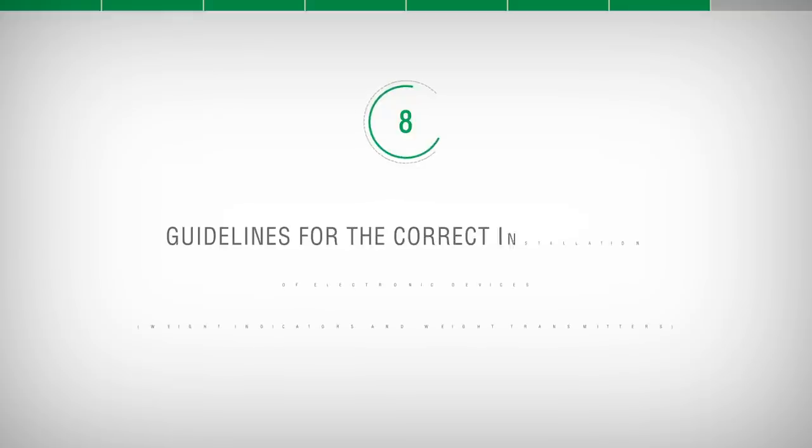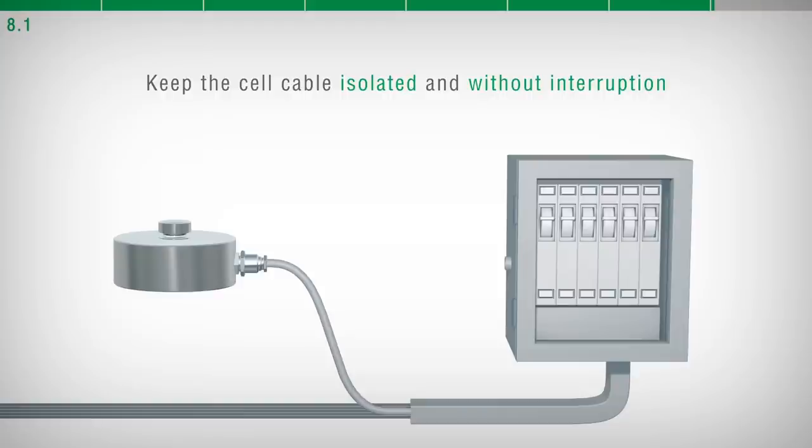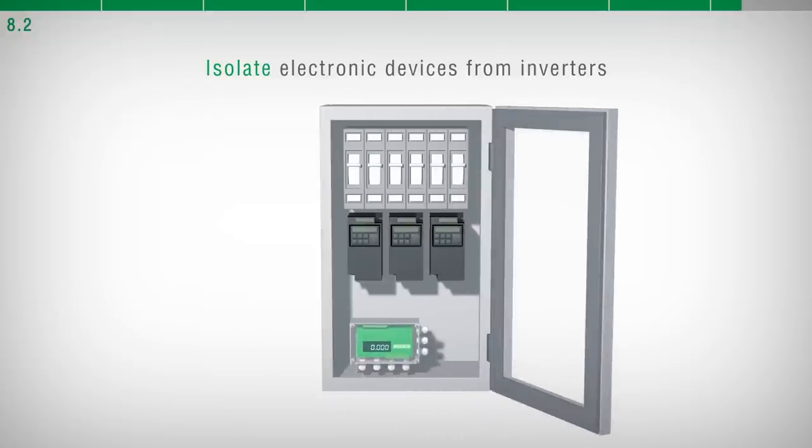Guidelines for the correct installation of electronic devices, weight indicators, and weight transmitters. The load cell cable must be autonomous and not pass through the wire way with other cables. It is recommended to connect it directly to the weight indicator or transmitter without interruptions and without terminal boards. It is recommended not to install electronic devices in an electrical panel containing inverters.